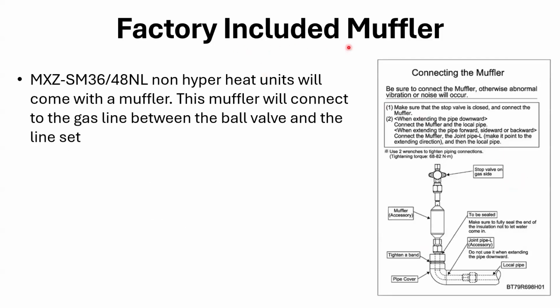Factory included muffler on these particular models. On the Smart Multi 36 and 48 non-hyperheat units will come with a muffler. This muffler will connect to the gas line between the ball valve and the line set. Because inside the unit, as you guys know, you have room to make that connection right to the service valve. So be sure to connect the muffler, otherwise abnormal vibration or noise will occur.